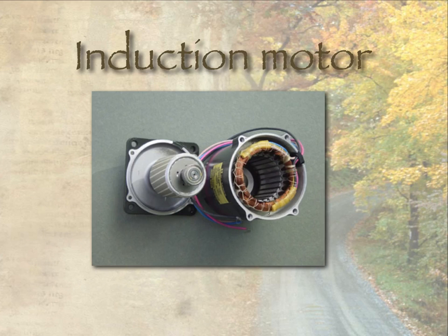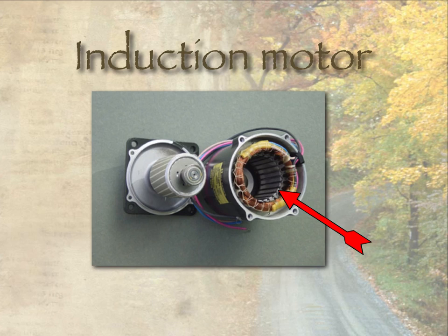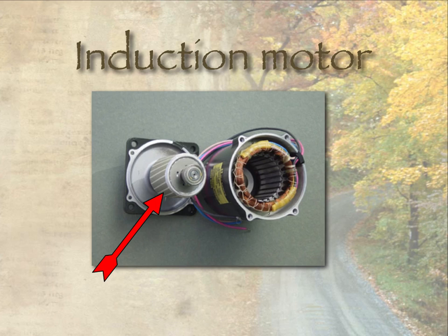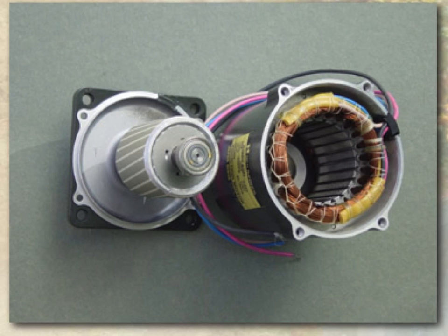In reality, the design is more complex. Rather than just four magnets, there is a whole series of electromagnets, all slightly out of phase with each other — not 90 degrees, but progressively out of phase. The rotor with the squirrel cage sits inside, where the eddy currents are produced, and the laminated core increases efficiency. That in essence is an induction motor.